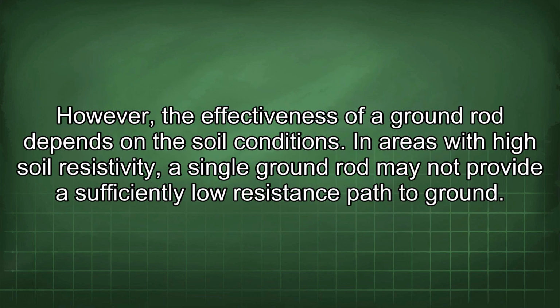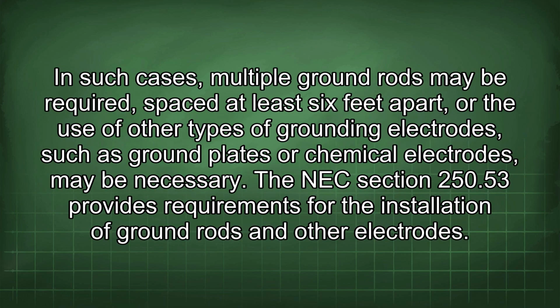However, the effectiveness of a ground rod depends on the soil conditions. In areas with high soil resistivity, a single ground rod may not provide a sufficiently low resistance path to ground. In such cases, multiple ground rods may be required, spaced at least 6 feet apart, or the use of other types of grounding electrodes, such as ground plates or chemical electrodes, may be necessary.